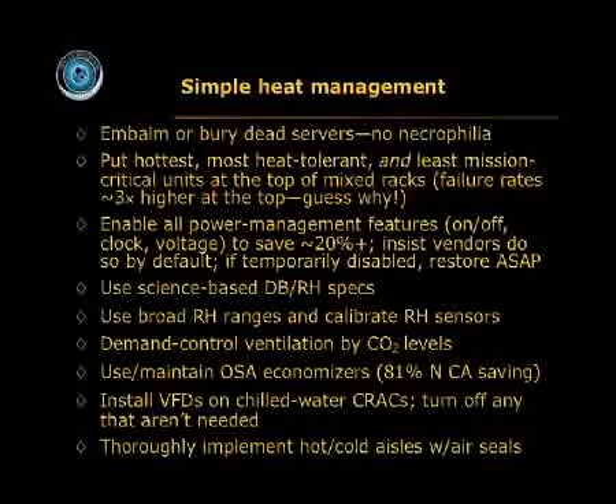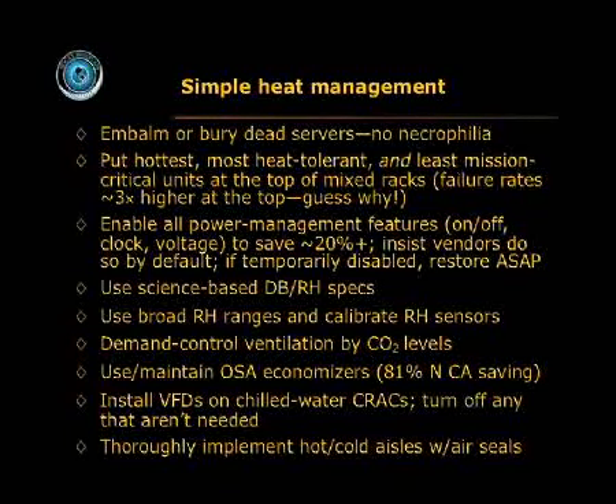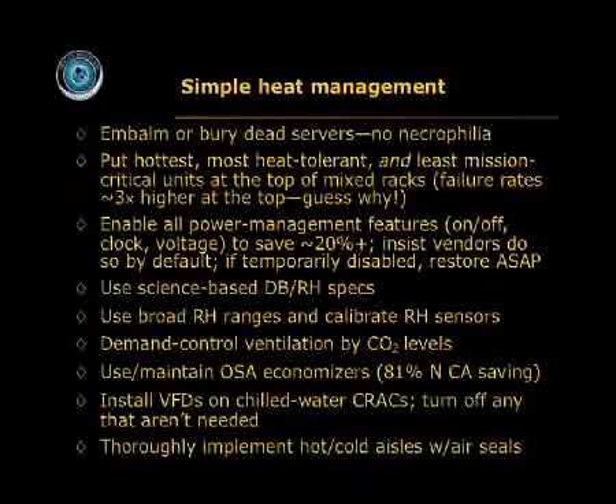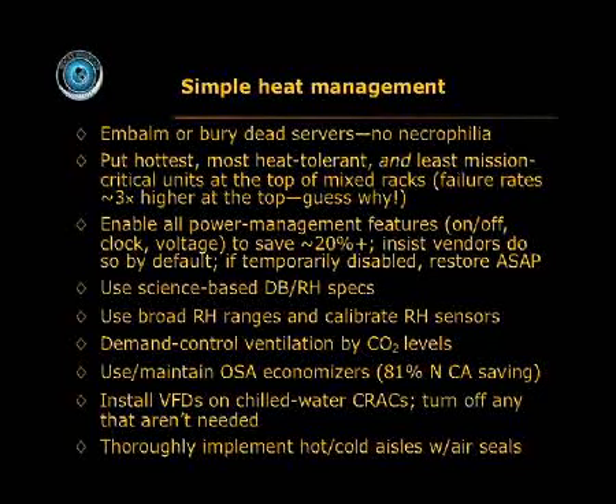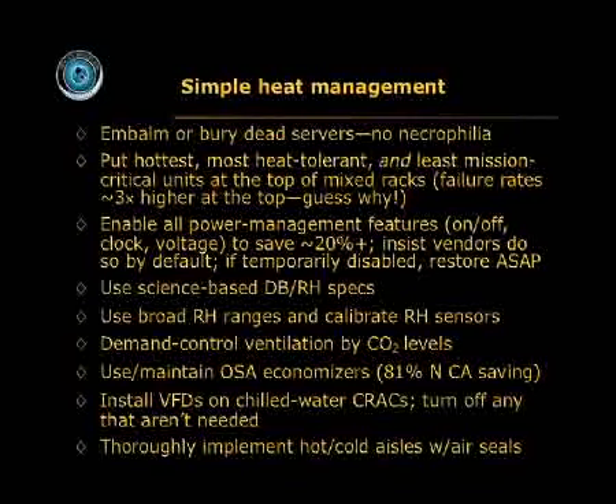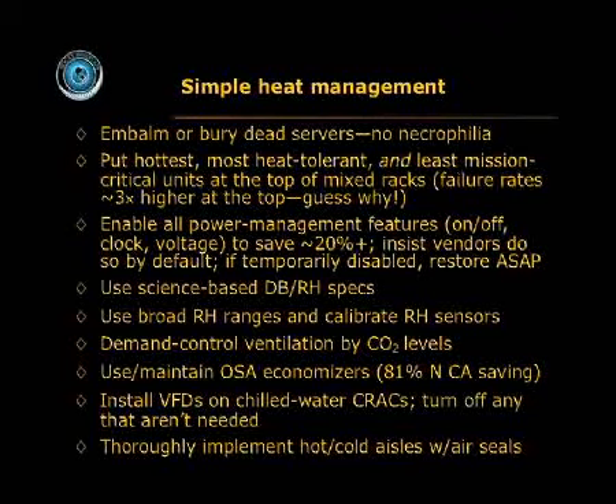We often have very tight RH control when we don't need it, and quite often you find it's fine to use a much broader range of RH and then make sure that you have calibrated sensors so you know what you've really got, because the sensors tend to drift. It makes sense to control ventilation by real-time CO2. Often there won't be people in the space and you don't actually need ventilation. You only need cooling, if that. Outside air economizers are good for an 81% saving in Northern California data centers. Much less here, but still interesting at times of year.